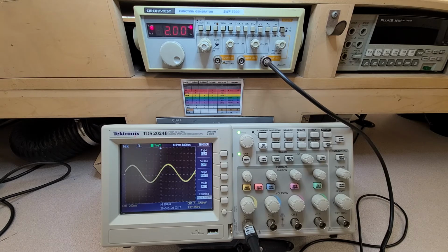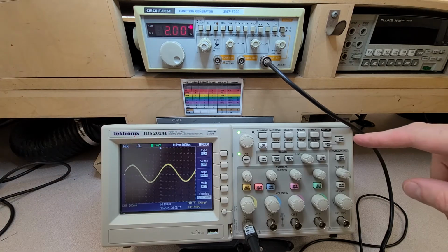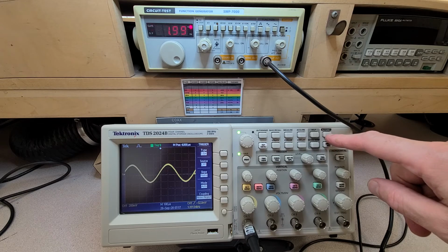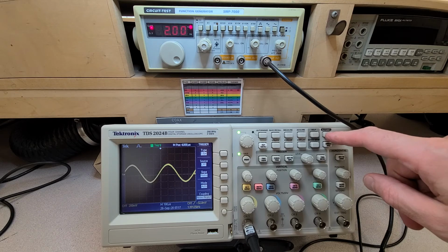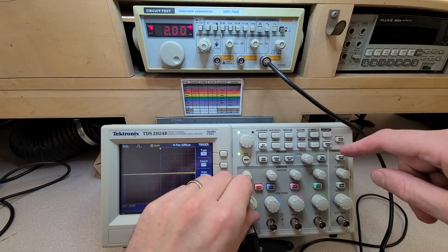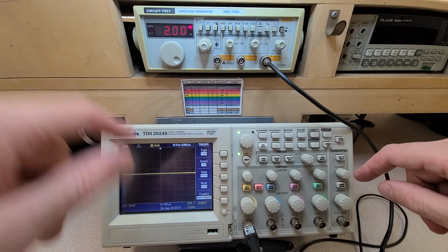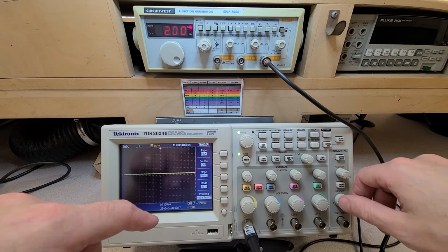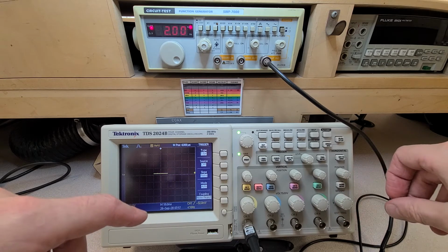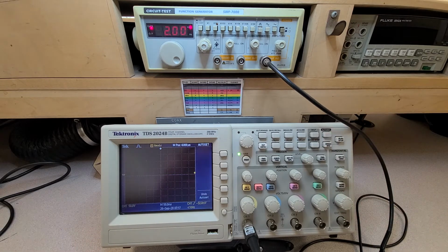Now, a lot of this seems pretty complex to set up, and it is, and it's worth learning how to set things up and how to control the scope. But there is a cheat button, because of course there's a cheat button in the digital world, and that's auto set right up here. So if you come in and you've got a brand new signal, let's just spin some dials right here. So there we go. We've got 50 volts per division, so we can't see it there. Let's change our timing so that that's all messed up right there. And you just press auto set.